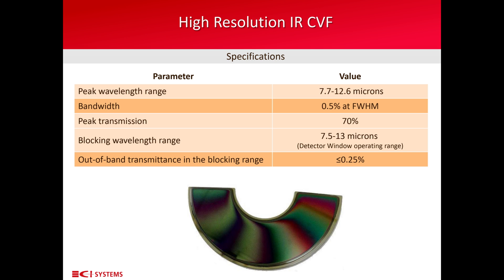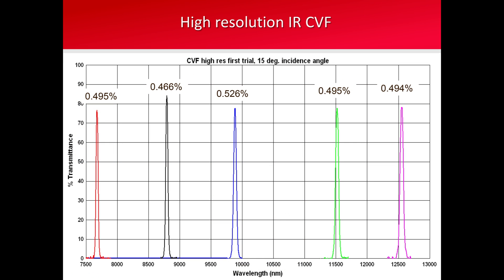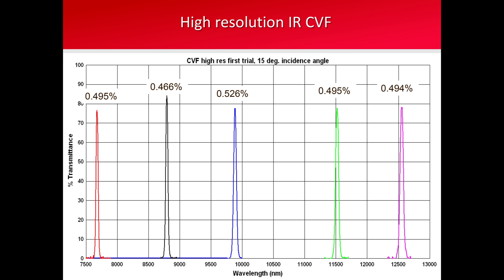We go down to 0.5% of the wavelength, whereas the types shown before in the previous slide, we get to spectral resolutions of 1.5 to 2% of the wavelength. Here in this slide, I show the measurement results of transmittance at different positions around the circumference of a high-resolution circular variable filter. We can see five peaks between 7.7 and 12.6 microns, all within the specification of 0.5% peak width.